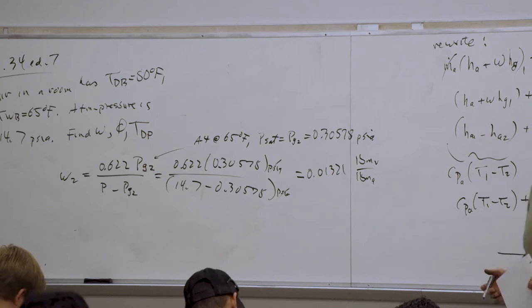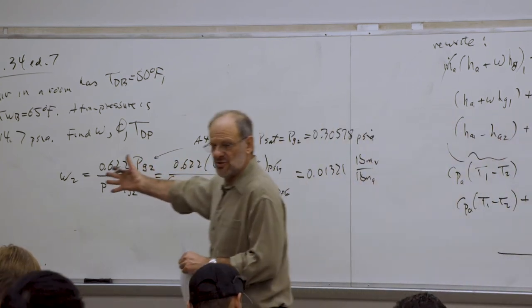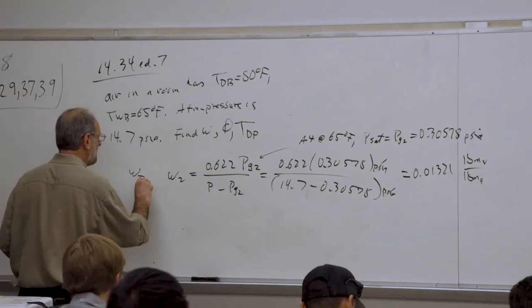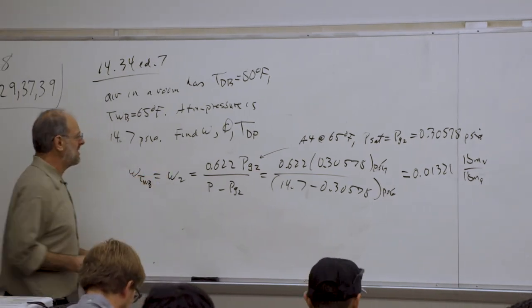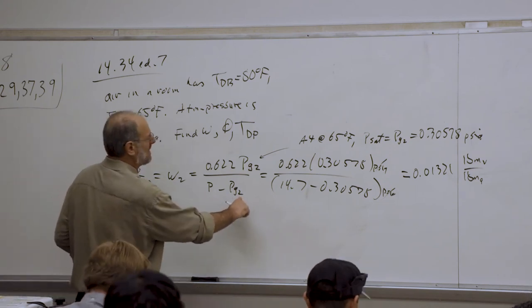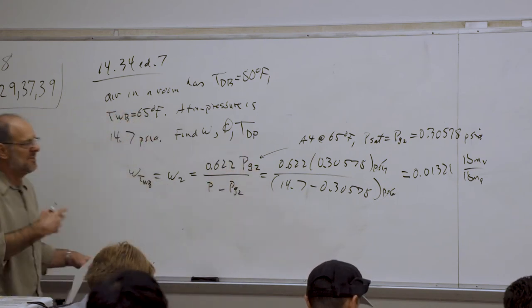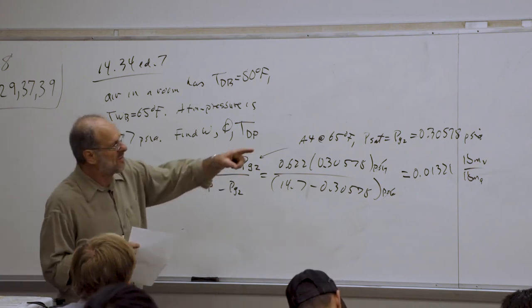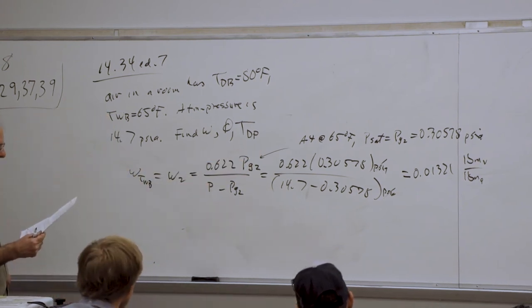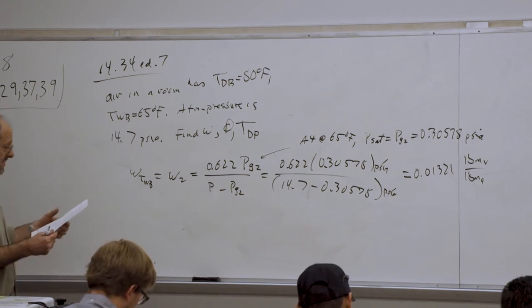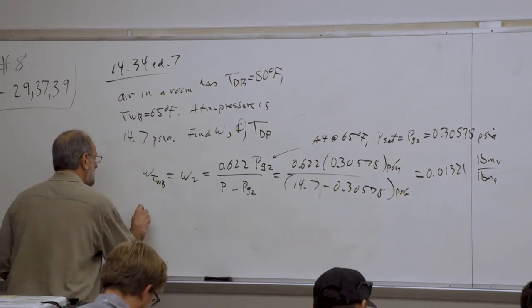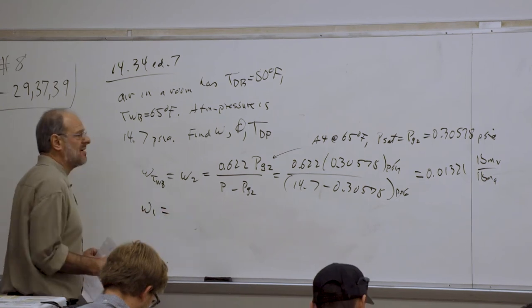Calculating: 0.622 times 0.30578 divided by (14.7 minus 0.30578), where both pressure values are in the same units and cancel. We end up with omega2 equal to 0.01321 pounds mass water vapor per pound mass of dry air.